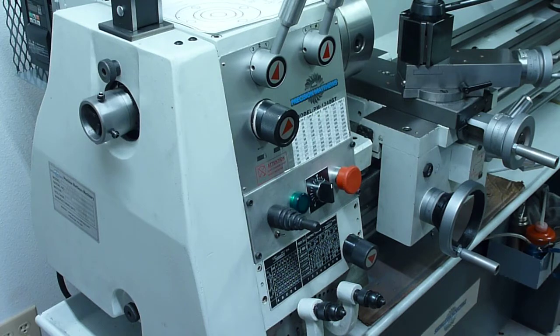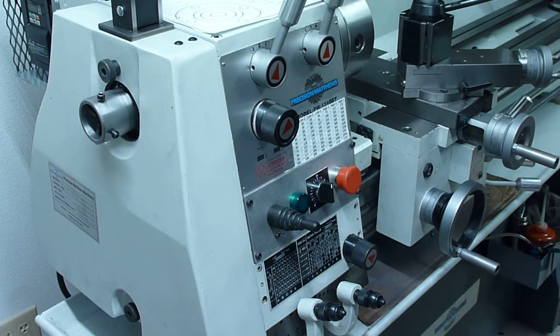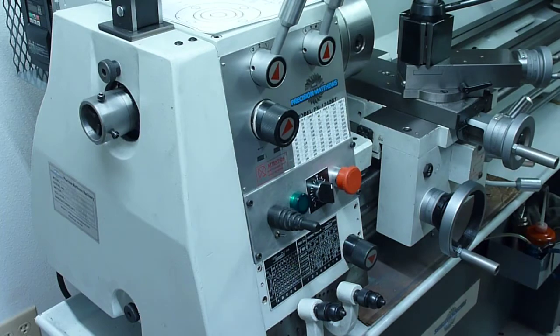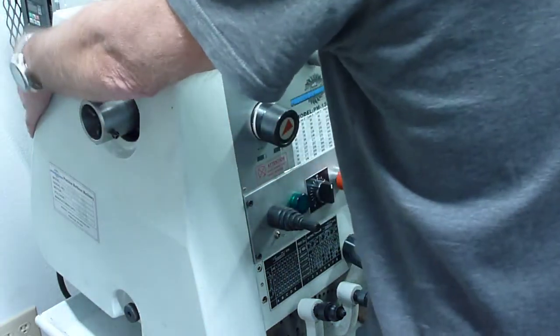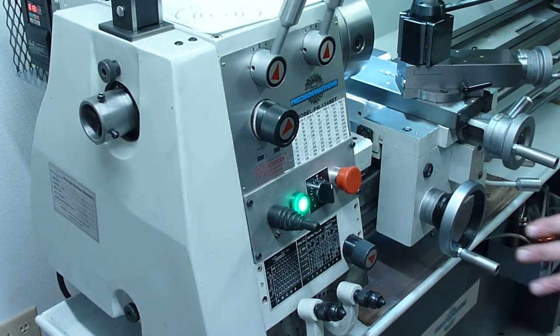Those two key safety features allow you to take on these two scenarios. Let's just say someone or you put the motor control switch in the on position with the lathe powered off. You should be able to walk up to the lathe, turn on the power to the VFD, and the lathe should not start.